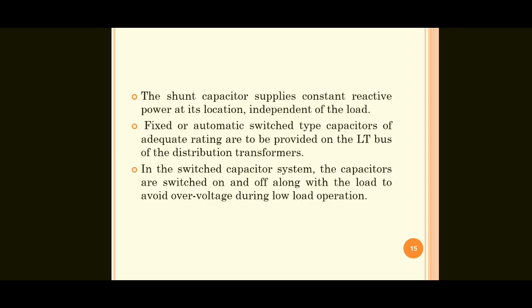So by using these capacitors, whenever over voltages occur at light load conditions or low load operation, the capacitors are switched on and off along with the load to overcome these difficulties. So here, the major components or main equipment of an 11 kV by 400 volt substation are the transformer mounting structure, protection system, earthing system, lightning arresters, LT distribution box and reactive compensation. Total 6 major components are present.